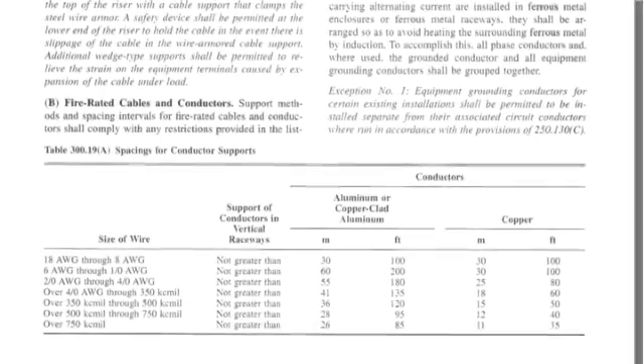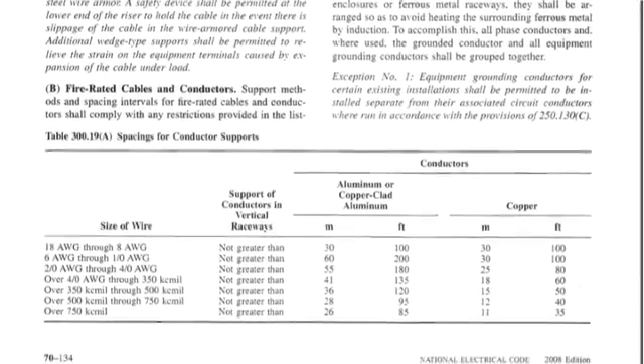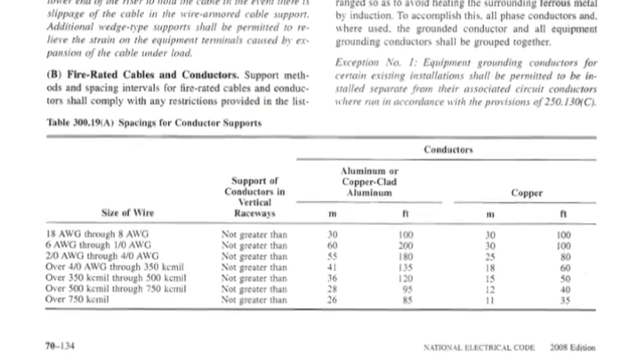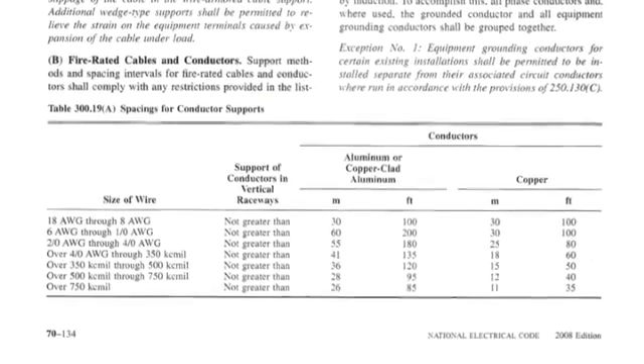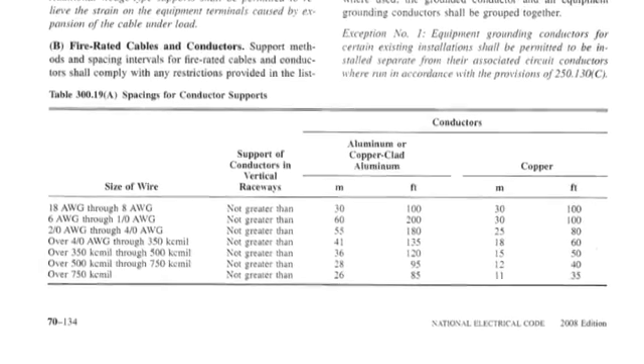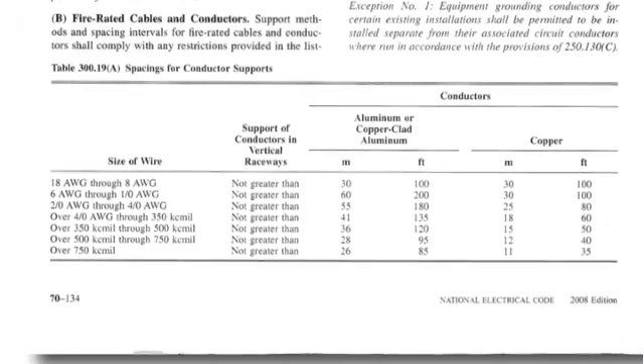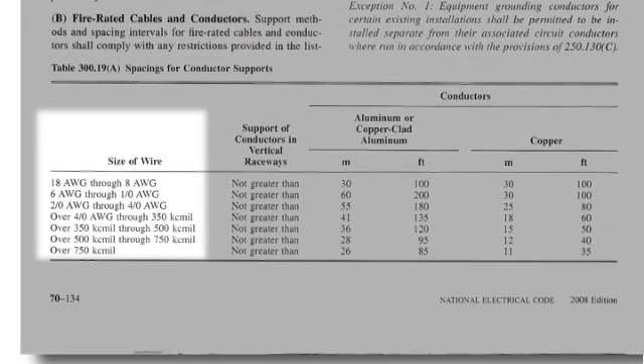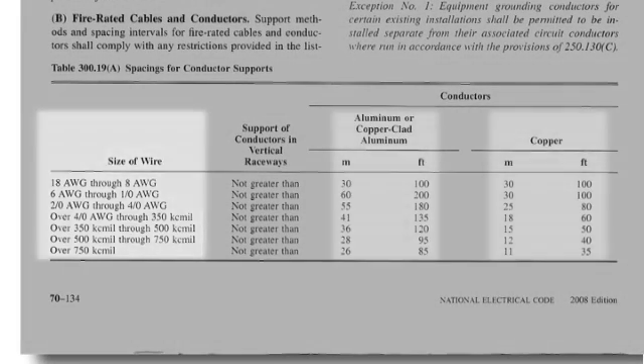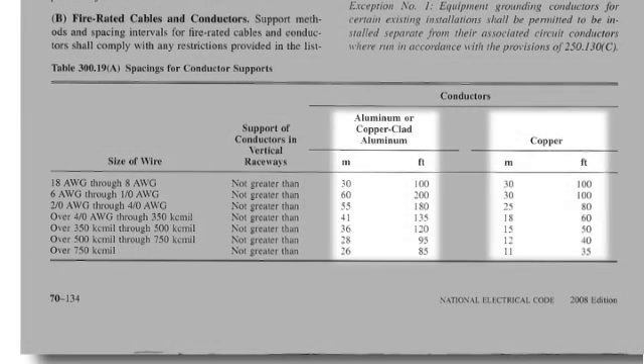Until now, contractors have had to find ways to combat the movement of conductors under the armor for riser installations by using the same rules that are used for supporting conductors in conduit. Supporting conductors inside a raceway are covered under NEC table 300.19. This table requires conductor supports based on both the size of the conductor and the conductor material.